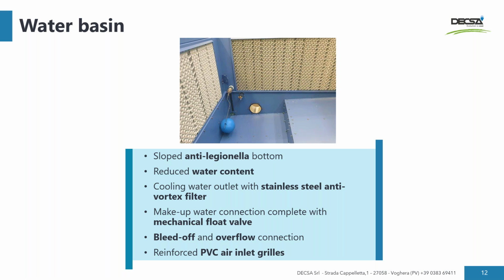Water basin or sump is the last but not least section of the SQA cooling tower. Also, the SQA series has been designed following the anti-legionella guidelines, so we have the sloped anti-legionella bottom. The water basin section is complete with a stainless steel anti-vortex filter on the water outlet, a mechanical float valve for the makeup water, and the bleed off and overflow connections. The air intake grills are made in reinforced PVC.